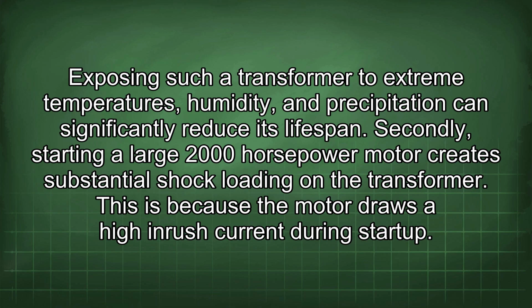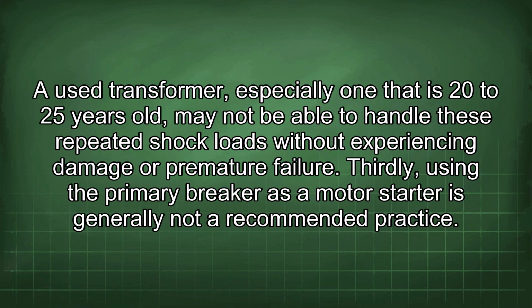Secondly, starting a large 2000 horsepower motor creates substantial shock loading on the transformer. This is because the motor draws a high inrush current during startup. A used transformer, especially one that is 20 to 25 years old, may not be able to handle these repeated shock loads without experiencing damage or premature failure.